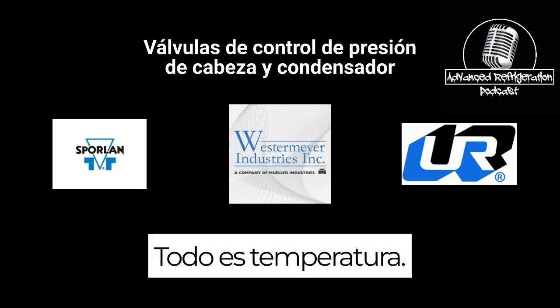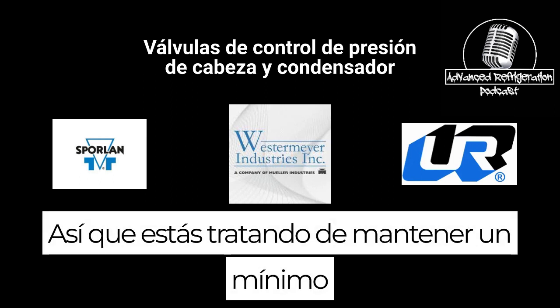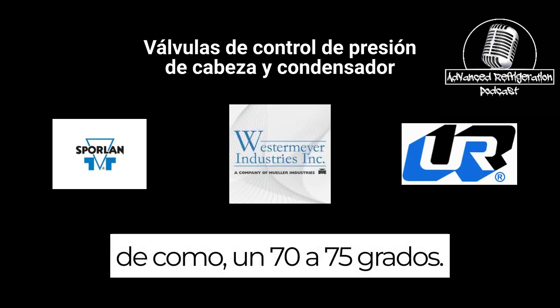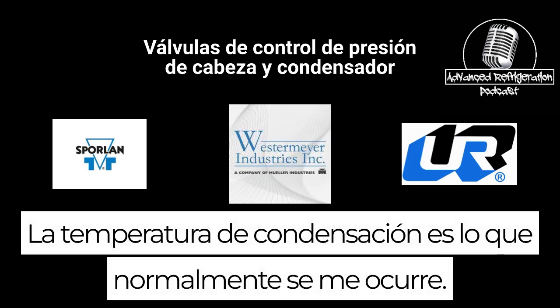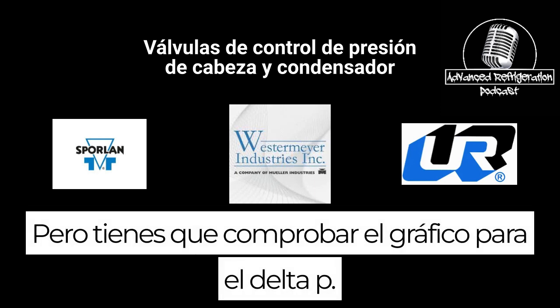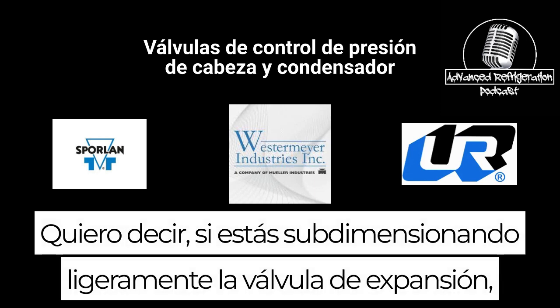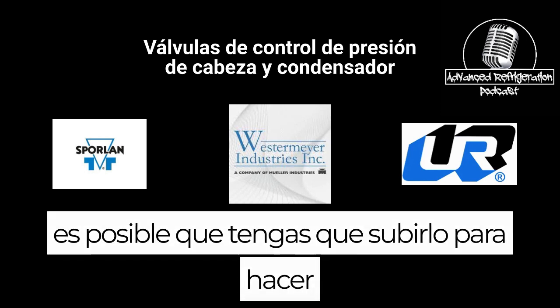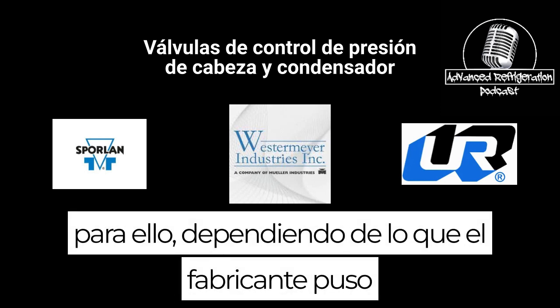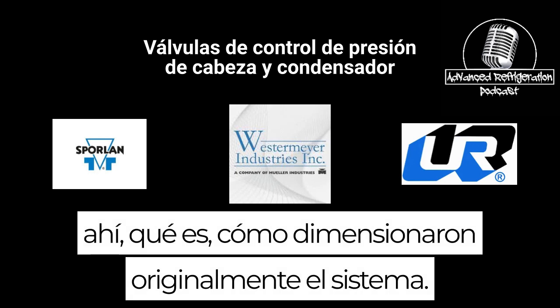It's all temperature. So you're trying to maintain a minimum of like a 70 to 75 degree condensing temperature is what I usually come up with. But you have to check the chart for the delta P. If you're slightly undersized in the expansion valve, you may have to bump it up to make up for it, depending on what the manufacturer put in there and how they originally sized the system.